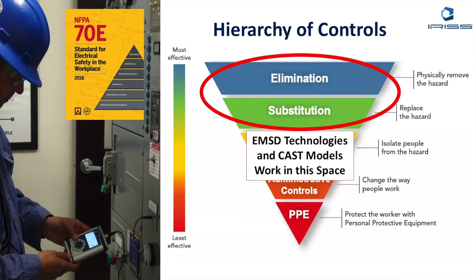In the following slides, we're going to look at a benefit analysis of an EMSD program installed in a paper mill. We utilized infrared inspection windows along with ultrasound and partial discharge inspection ports. We looked at the actual program — it covered 150 pieces of primary switchgear that were on an annual inspection program.